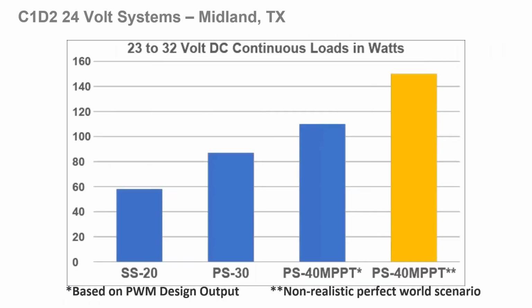Now we're going to go through the same exercise at 24 volts. You can see just due to the jump in DC voltage on the charge controller ratings, they inherently support essentially twice the array, thus twice the load, because of that doubling in the voltage rating. So a very similar chart, but ultimately higher values.